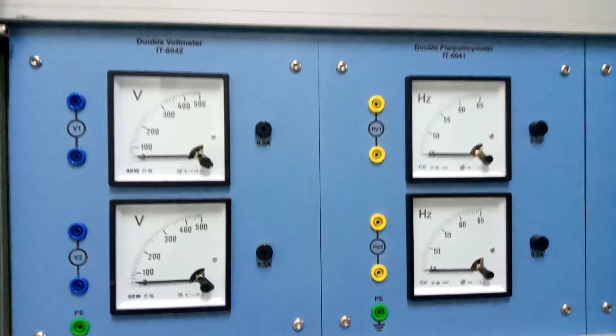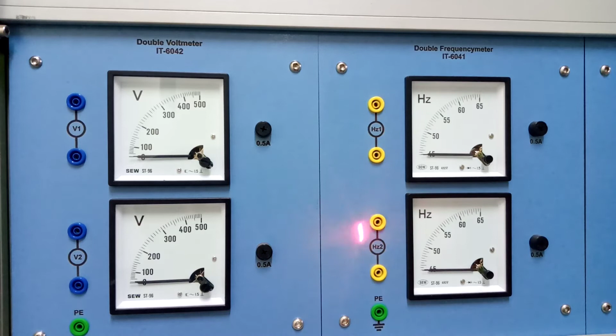Next we have a double voltmeter, connected in shunt or parallel with your supply, with a range from 0 to 500 volts for both, and a fuse also installed. We also have a double frequency meter, with a range from 45 to 65 hertz, and as you know for 220 volts we have a 50 hertz frequency system. One will be used for the bus bar, and the other for the generator.